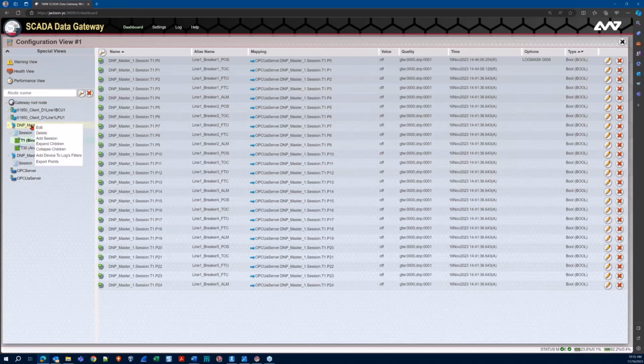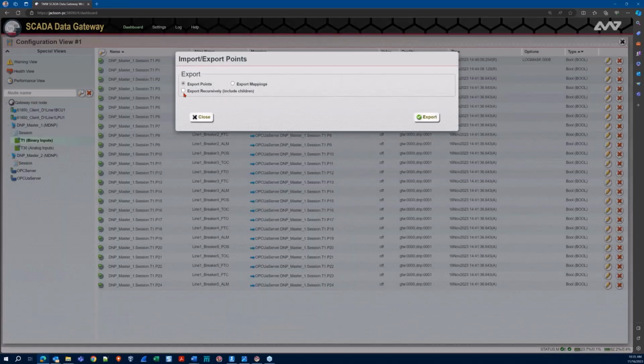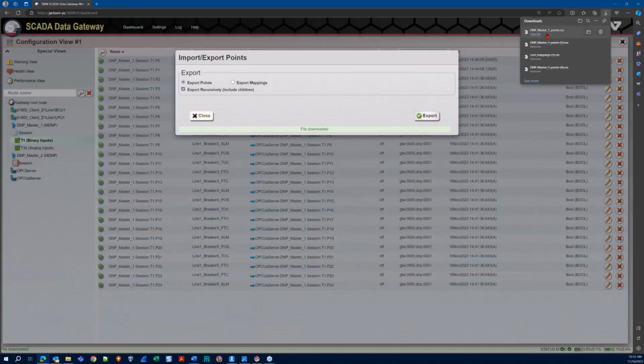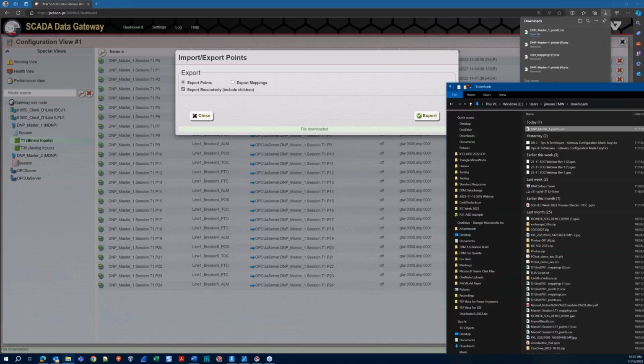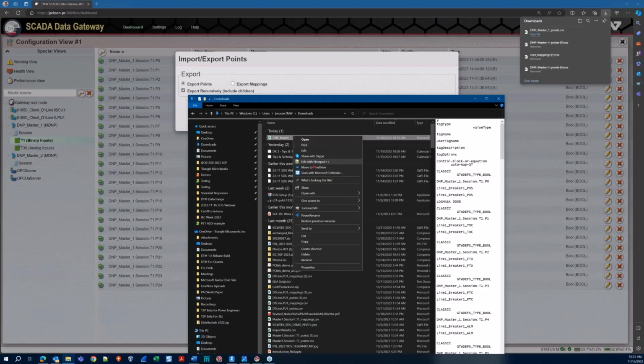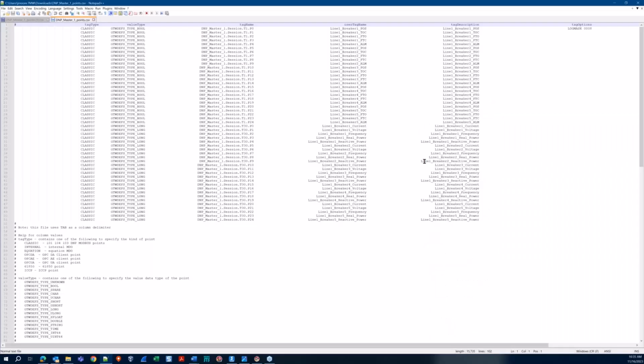In order to do that, I just need to right click on the device itself, so DNP Master 1, and I'm going to export the points. So I do need to make sure that I say recursive include children, and that's just because session as well as the point types, binary inputs, and analog outputs are children of the root, which is the DNP Master 1 device. And I'll just go ahead and hit export. When I do that, it exports the file out to my downloads folder, and I can just right click and open that up in Notepad++.